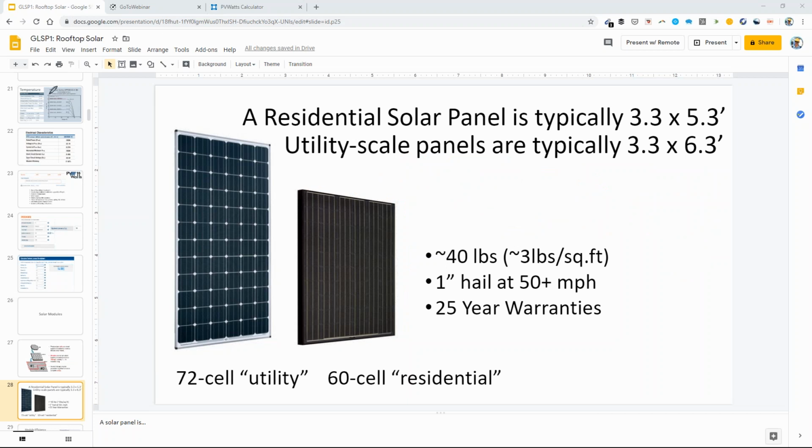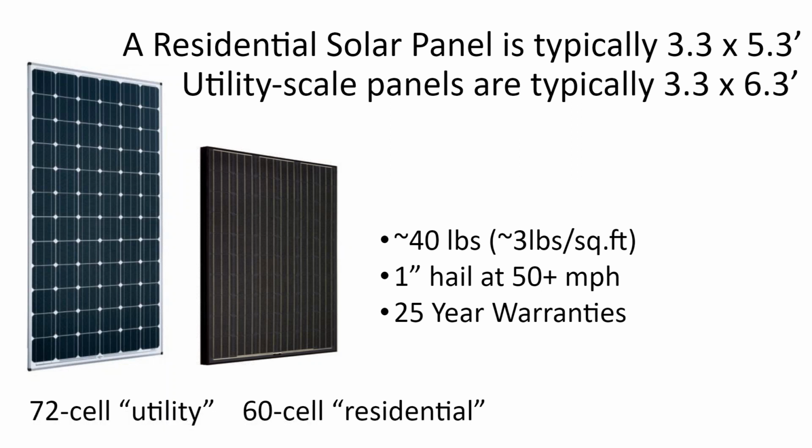And the reason why that number is interesting is most 1 and 2 story tall buildings consume far less than 22 kilowatt hours per square foot, closer to 7 or 8. And so what that means is that, if you cover a rooftop of a building with solar, solar can produce enough power to offset the electrical consumption of most 1 or 2 story buildings if they have an easy enough rooftop to put a solar array on, which I think is pretty phenomenal. I mean, that means if we have solar across the rooftop of a city, that could be the power plant. Not trying to comment on yet if that's cost effective or not, just technically it's capable.